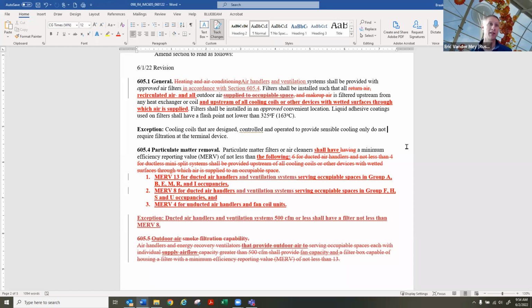I guess I'm going back to my question: do we need an exception for energy recovery unit relief and exhaust air that's coming back? Is the intent to provide MERV 13 filtration on the return side of the ERV? As I currently read this, that's what you'd have to do in a Group R occupancy. Because you have to have a filter in accordance with 605.4, the ERV is serving an occupiable space, it's a ventilation system, and I have to have a filter upstream of the heat exchanger on the return, on the relief/exhaust side. So now I need to provide MERV 13 filtration on that if I'm more than 500 CFM.